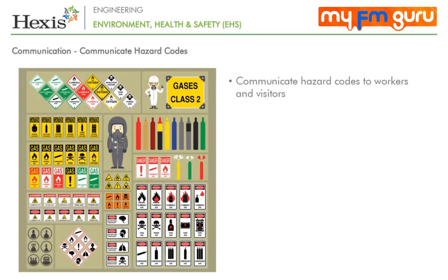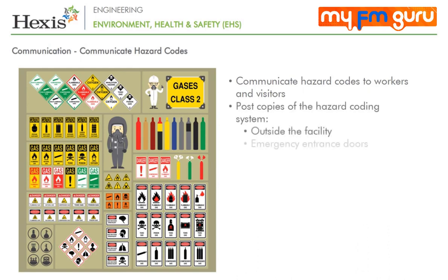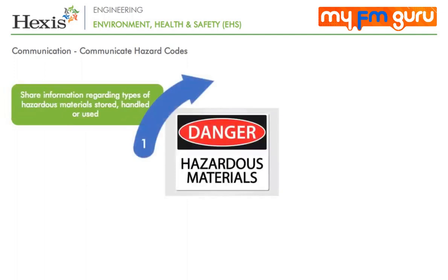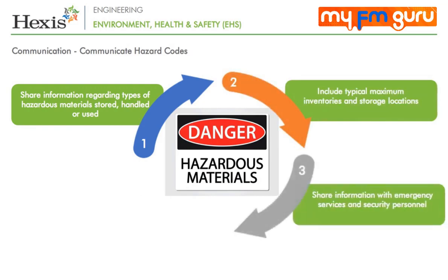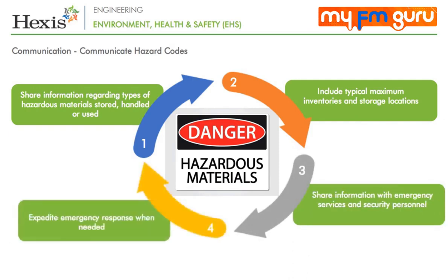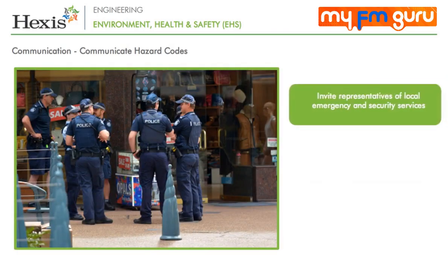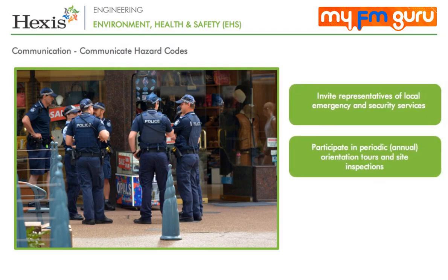Communicating hazard codes to workers and visitors is necessary. Copies of the hazard coding system should be posted outside the facility at emergency entrance doors and fire emergency connection systems. Information regarding types of hazardous materials stored, handled or used at the facility, including typical maximum inventories and storage locations, should be shared proactively with emergency services and security personnel. Representatives of local emergency and security services should be invited to participate in periodic annual orientation tours and site inspections to ensure familiarity with potential hazards.